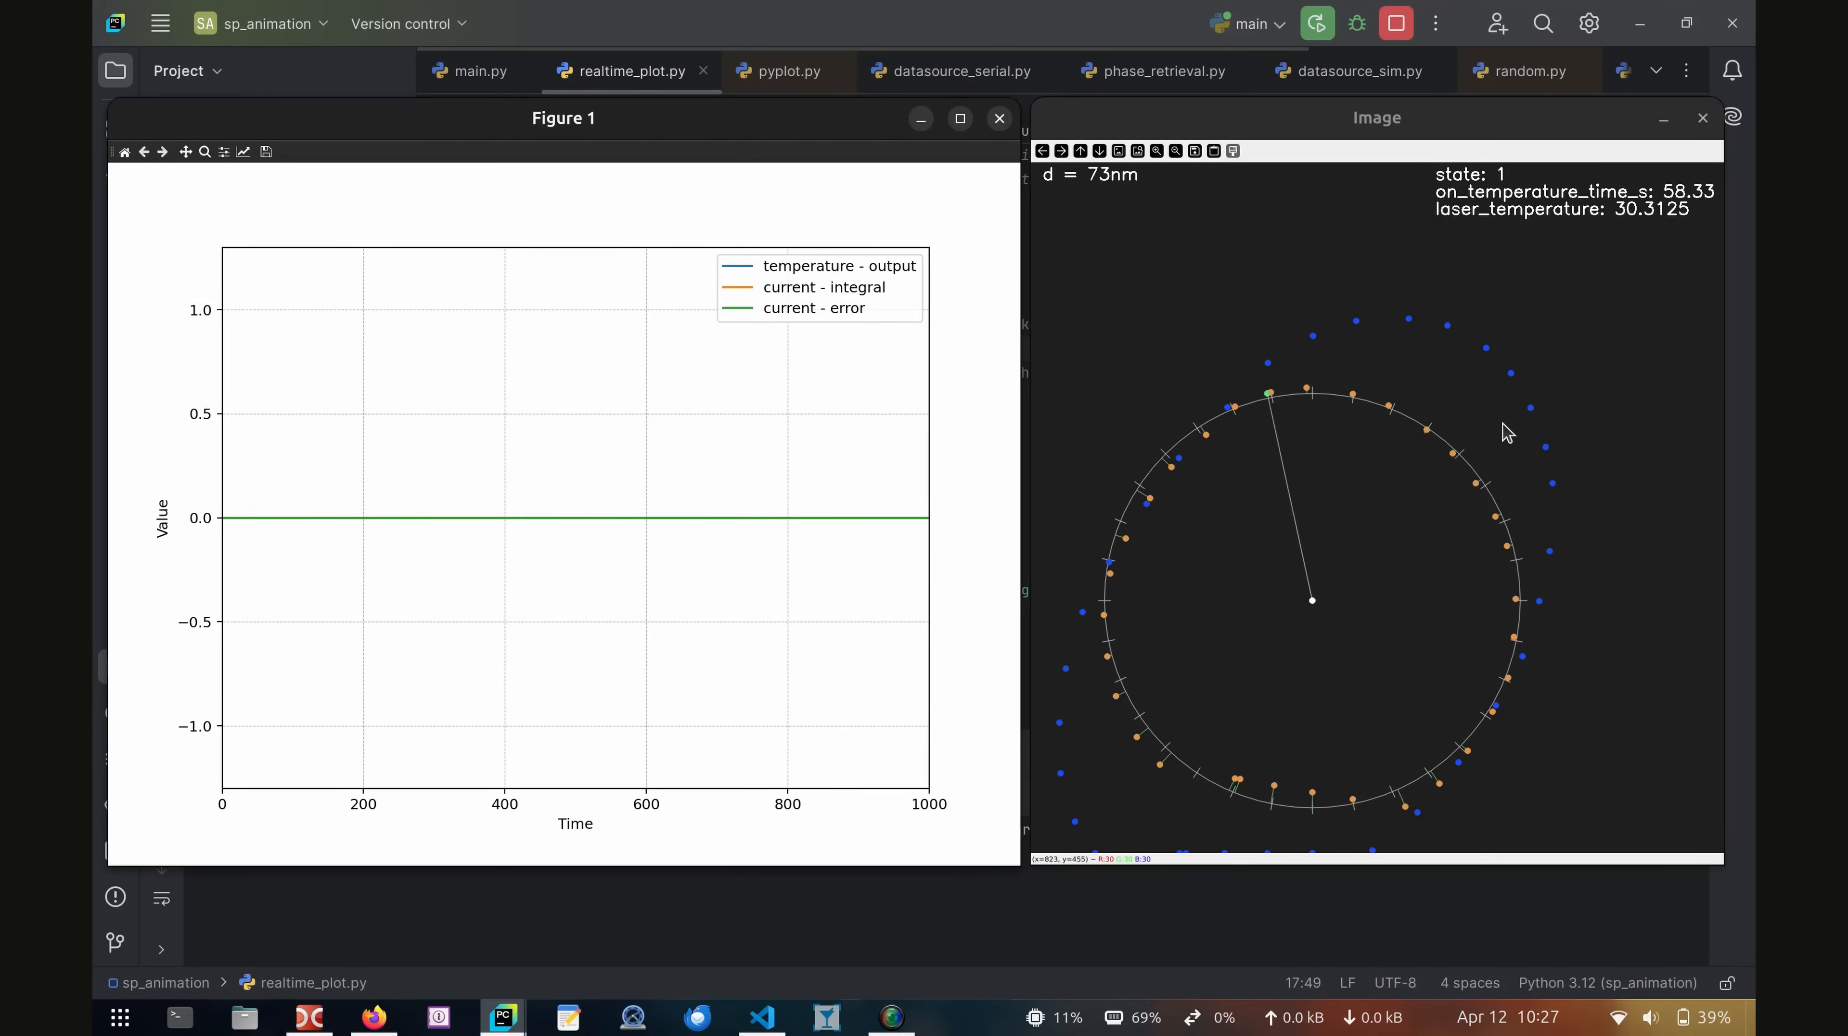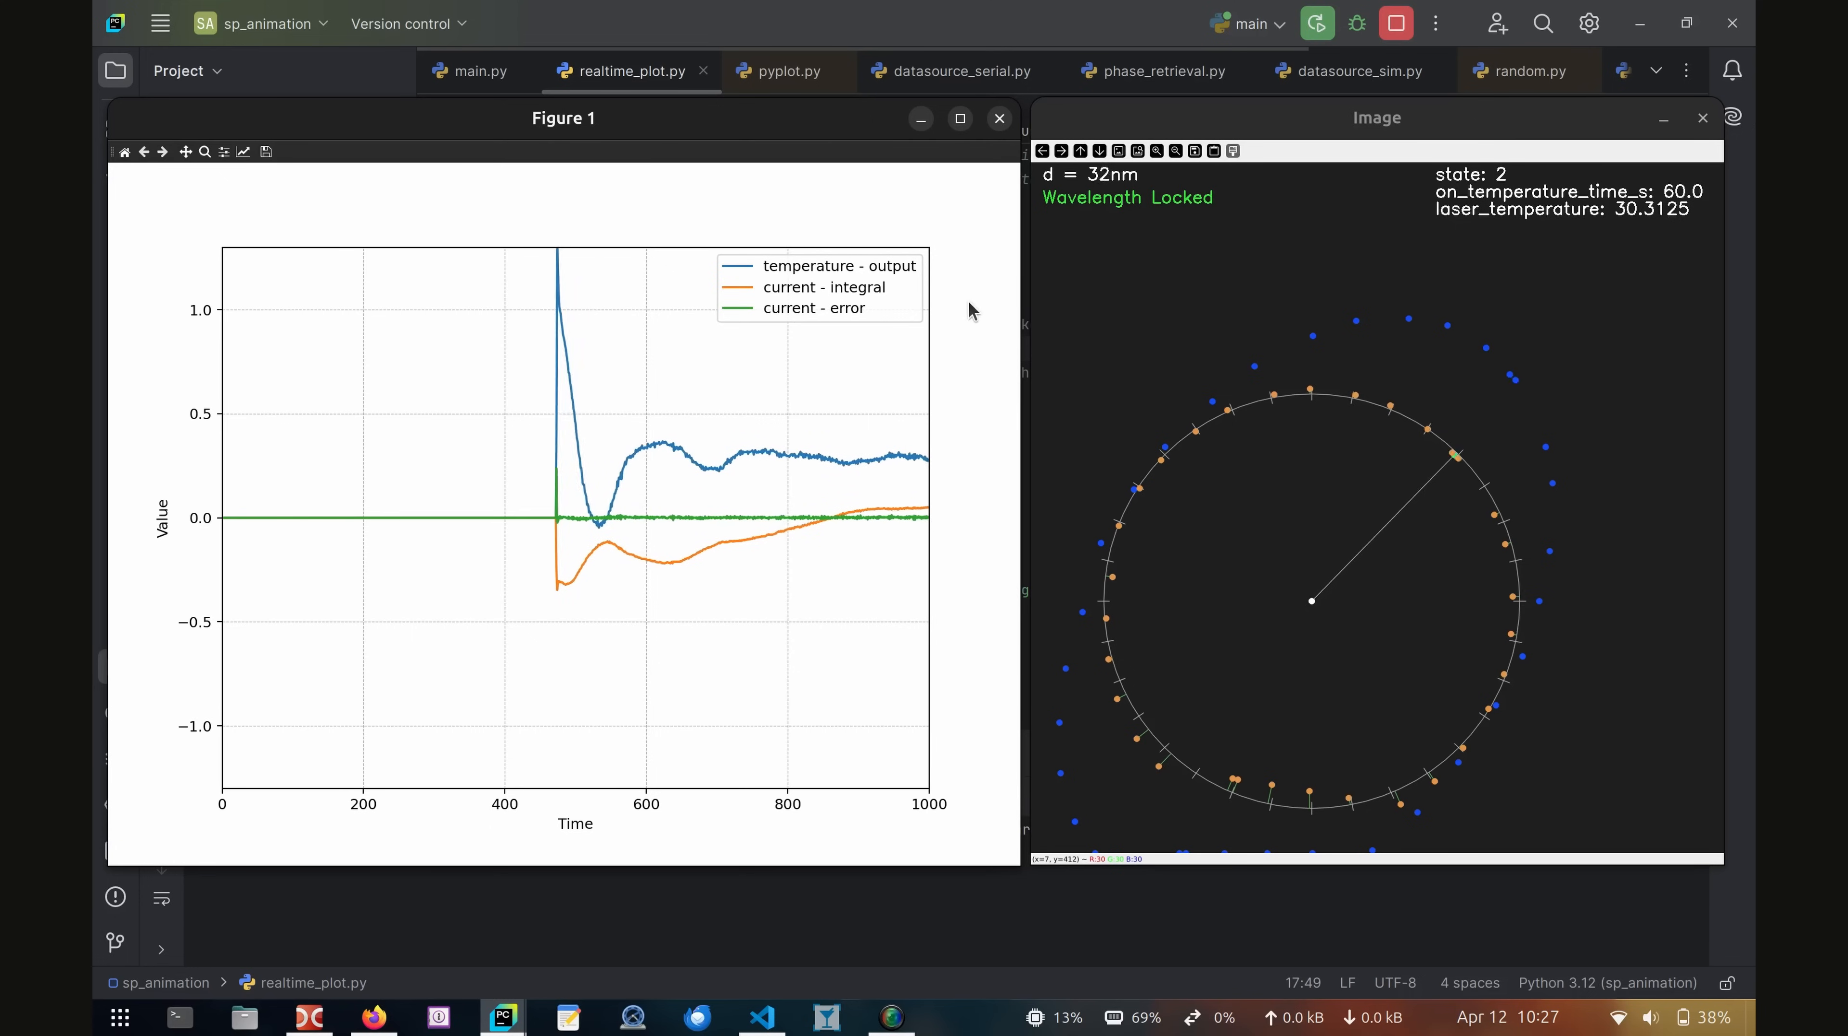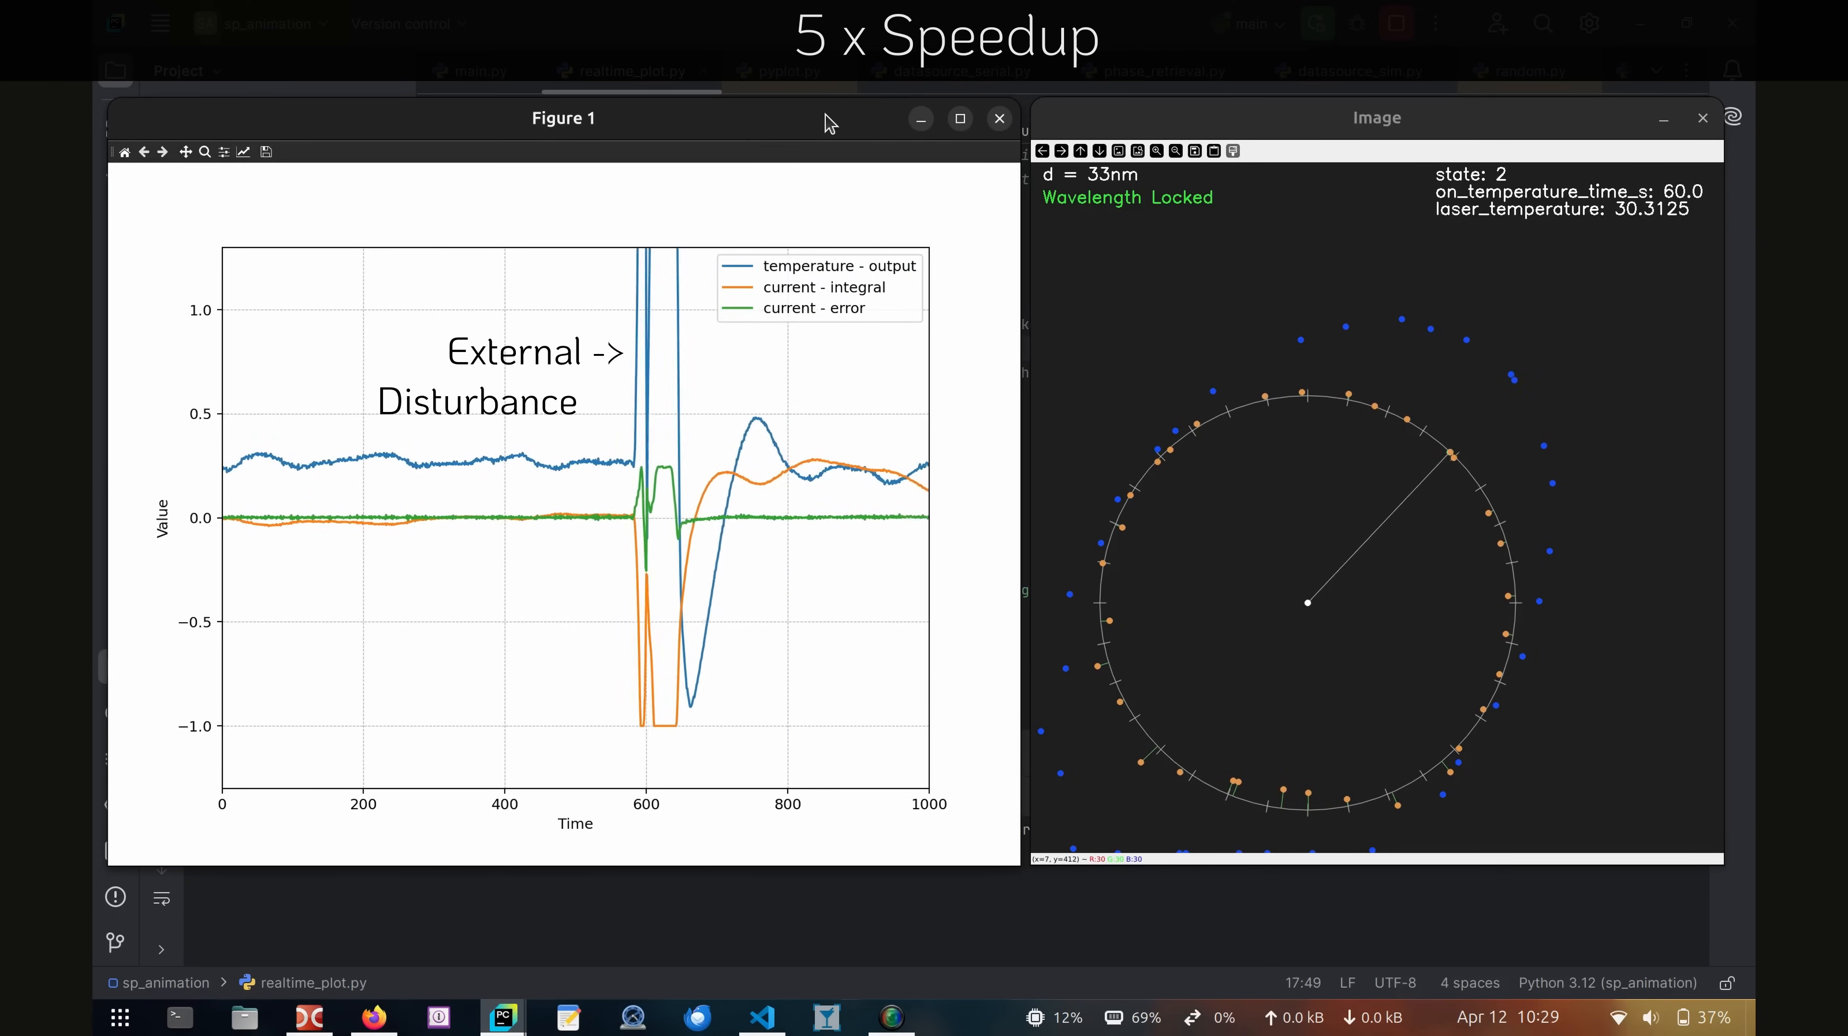To prevent this issue, we use the heater in a secondary control loop to desaturate the current controller. In other words, a second controller adjusts the temperature with the goal of driving the integral term of the current controller towards zero. Here on the left, the integral term of the current controller is shown in orange. The output of the wavelength temperature controller is shown in blue. Note that the initial temperature controller used during startup is now disabled, and the temperature sensor is no longer used during wavelength control. You can observe that the integral term is gradually reduced towards zero over time. With this control scheme, the temperature of the laser diode can be maintained with very high precision, and disturbances are compensated much more quickly by the current controller than would be possible with temperature control alone.